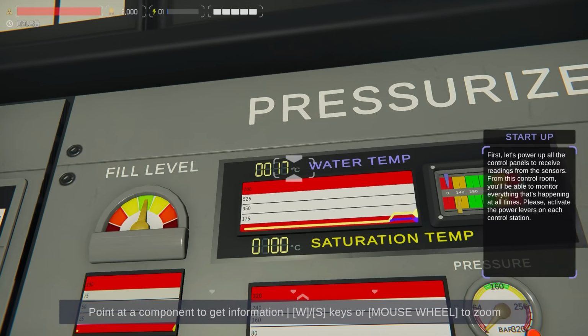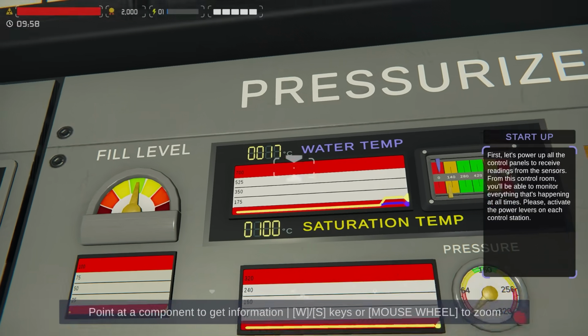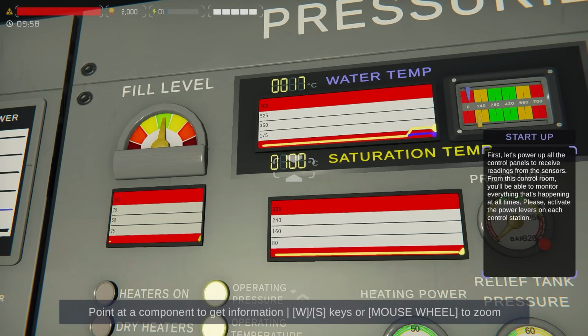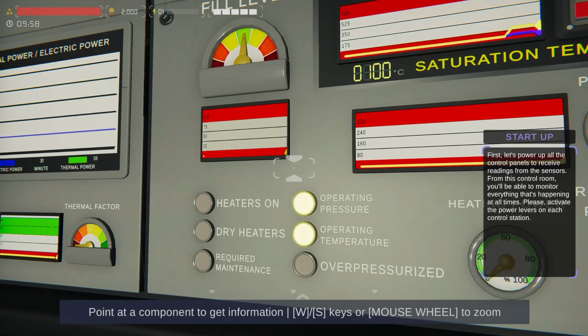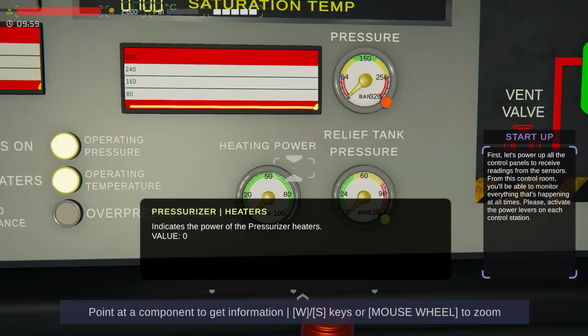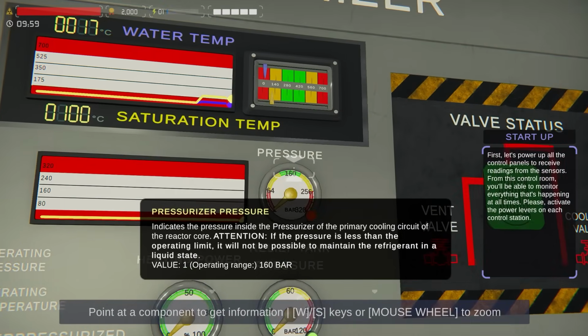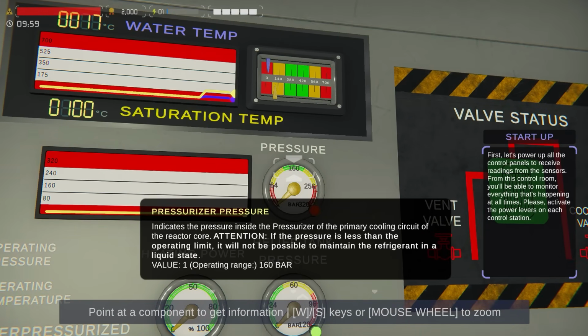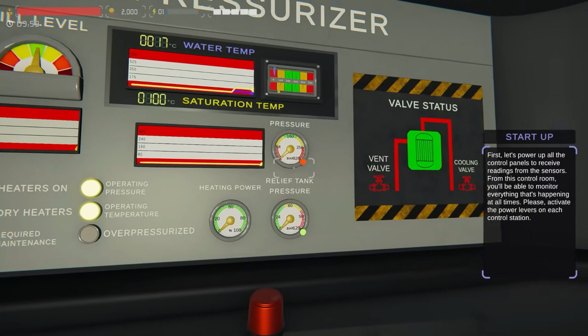So water temperature is at 17 degrees Celsius, and the saturation temperature is at 100. Fill level is fine, and everything else seems to be normal. Pressure needs to be ideally in the 160 range there, 160 bar, not PSI.